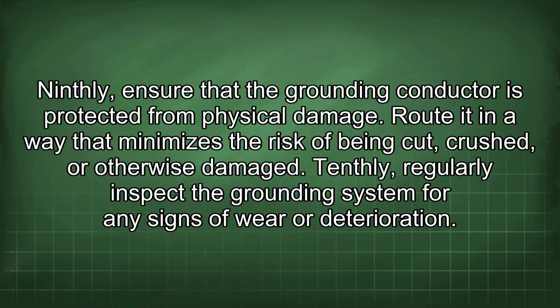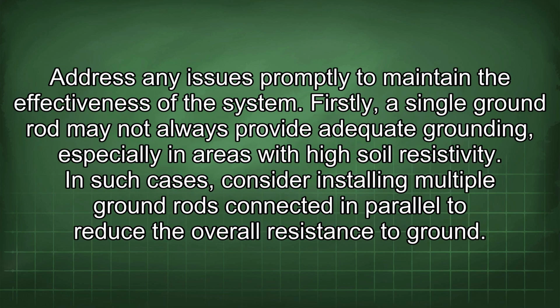Ninthly, ensure that the grounding conductor is protected from physical damage. Route it in a way that minimizes the risk of being cut, crushed, or otherwise damaged. Tenthly, regularly inspect the grounding system for any signs of wear or deterioration. Address any issues promptly to maintain the effectiveness of the system.